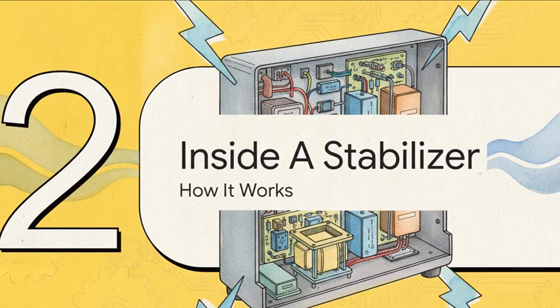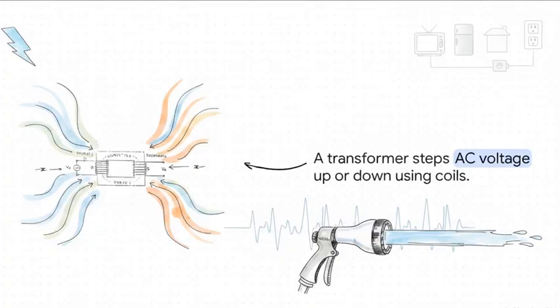Let's move to section 2, inside a voltage stabilizer. At the very heart of this system, we have a basic transformer. This uses a primary coil and a secondary coil, both wound around the exact same iron core, to step the AC voltage up or down. Think of it kind of like adjusting a nozzle to control the water pressure in your garden hose. By changing the ratio of the turns of wire between the primary and secondary coils, the transformer mechanically alters the voltage to the exact level you need.